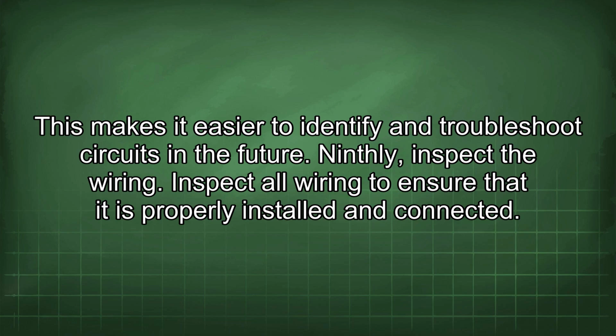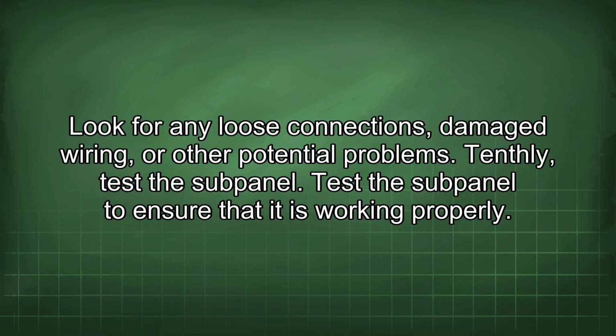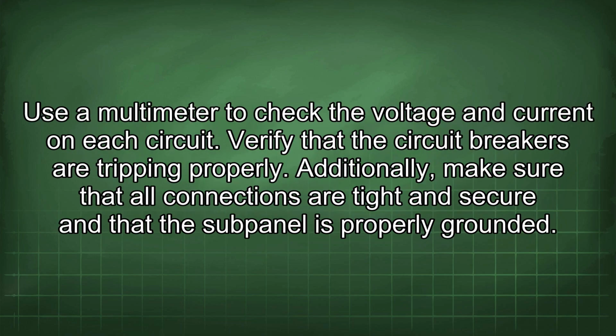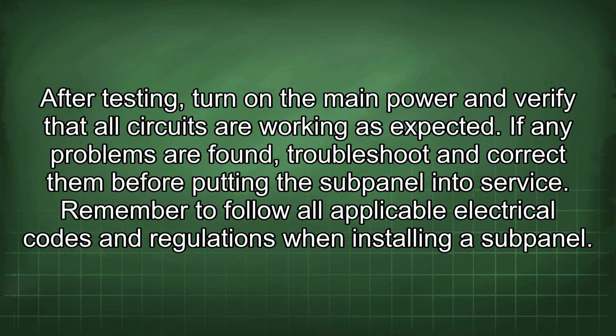Ninthly, inspect the wiring. Inspect all wiring to ensure that it is properly installed and connected. Look for any loose connections, damaged wiring, or other potential problems. Tenthly, test the sub-panel. Test the sub-panel to ensure that it is working properly. Use a multimeter to check the voltage and current on each circuit. Verify that the circuit breakers are tripping properly. Additionally, make sure that all connections are tight and secure and that the sub-panel is properly grounded. After testing, turn on the main power and verify that all circuits are working as expected.